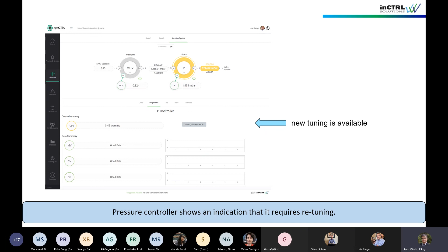You can go through the software and look at the tuning suggestions the algorithm provides, compare them to your current tuning settings, and see whether the controller should be a little more or less aggressive depending on the algorithm's advice. Then you can adjust that tuning manually if you like, using expert knowledge to tweak relative to what the algorithm gave you.